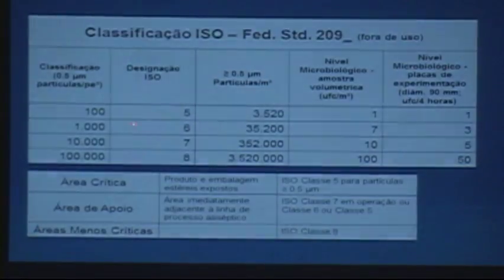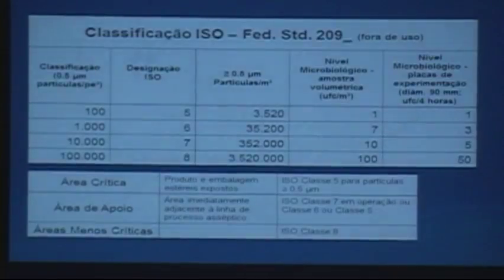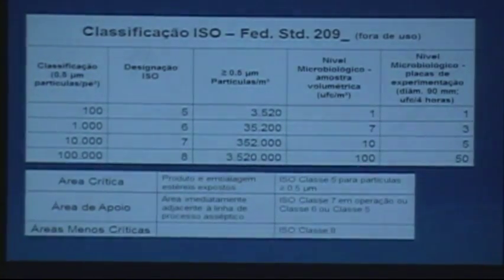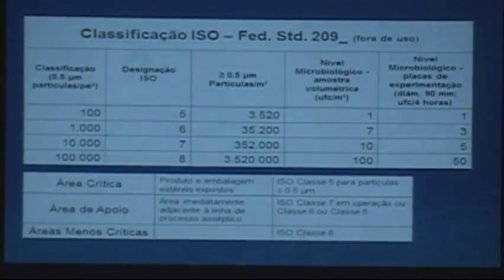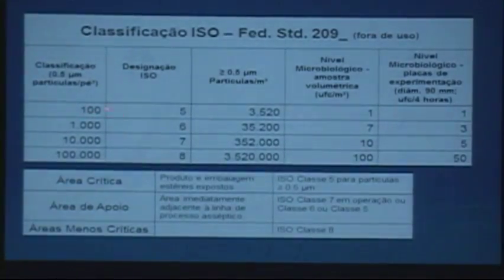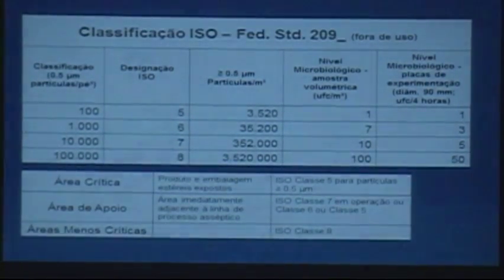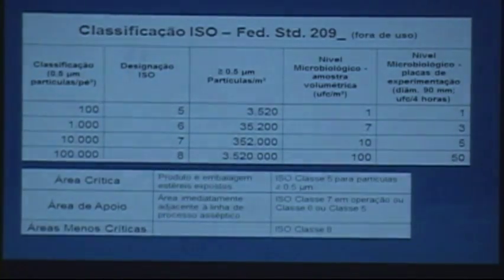The pharmaceutical industry mainly adopted this Federal Standard — an American norm. Now it is the ISO norm that prevails, correlated with ANVISA — mainly for laboratories. The way to classify rooms is by particle count per cubic meter, whereas before it was per cubic foot. I can only achieve class 100 or class 5 with unidirectional flow, and it is expensive.